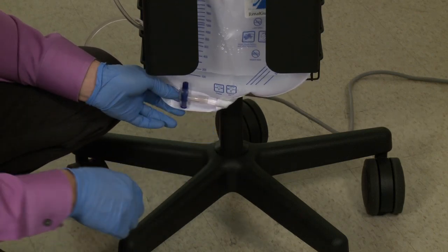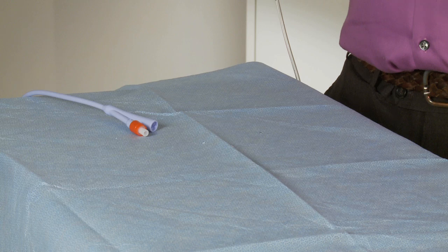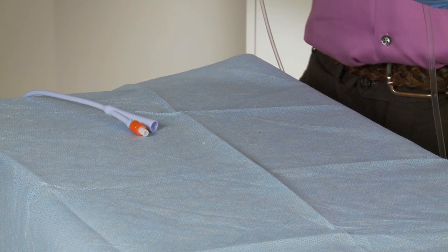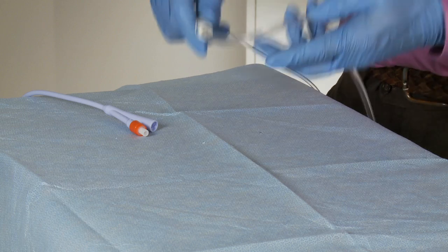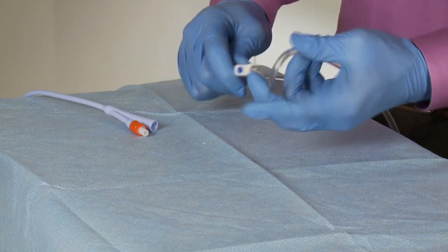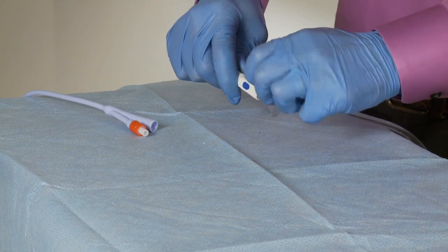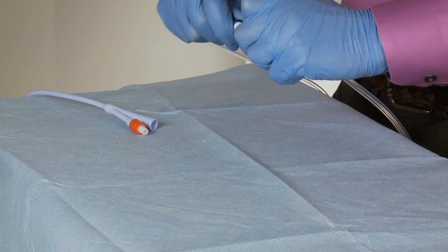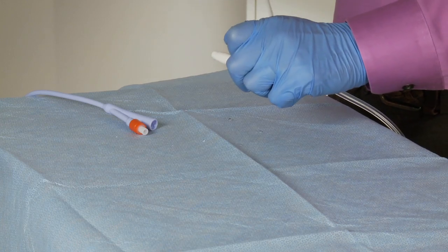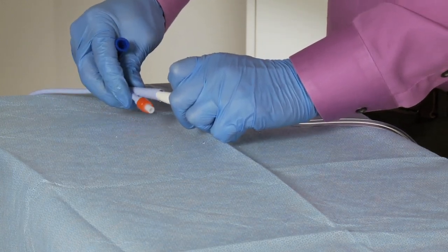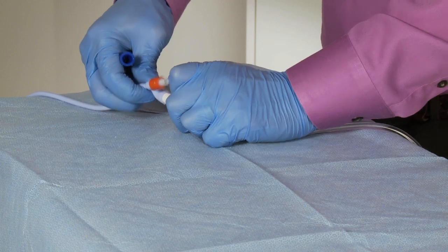We are now ready to connect a single-use set to the patient. Any size Foley catheter can be used. Kink the urine line, if possible, to prevent the saline from draining into the bag. Keeping saline in the collection line improves the accuracy of RenalGuard's urine measurement. Disconnect the blue priming adapter. Connect the Foley connector of the collection set to the urinary catheter.